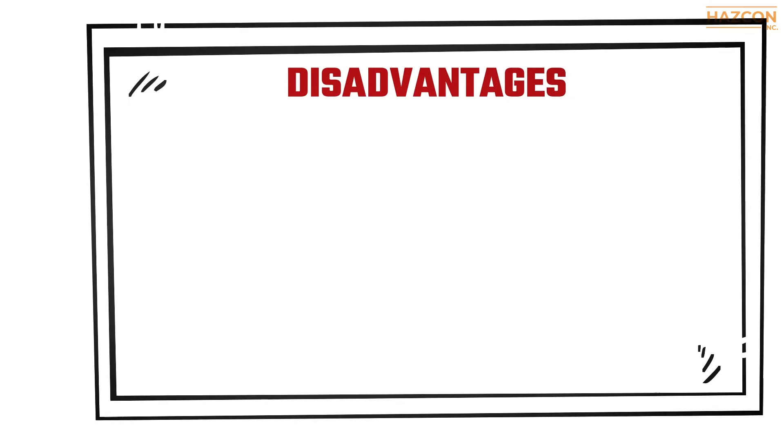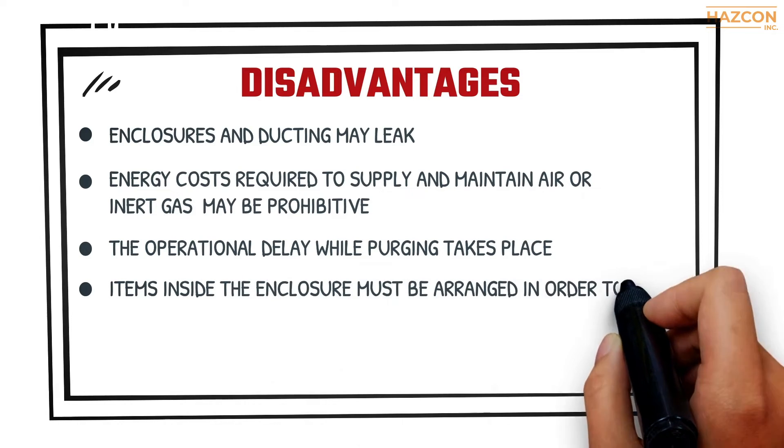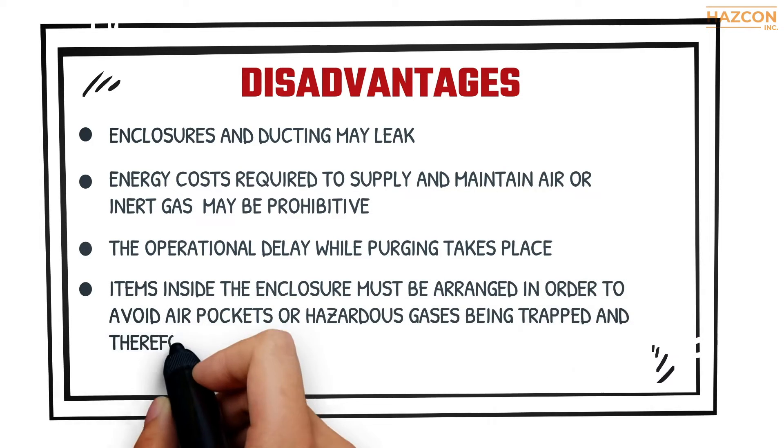The disadvantages include: these enclosures and ducting may leak, energy costs required to supply and maintain air or inert gas may be prohibitive, the operational delay while purging takes place, and items inside the enclosure must be arranged in order to avoid air pockets or hazardous gases being trapped and therefore not adequately purged.